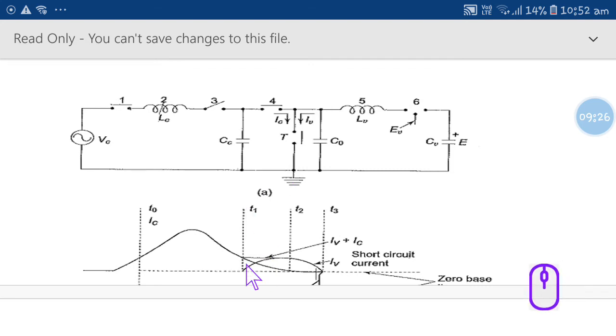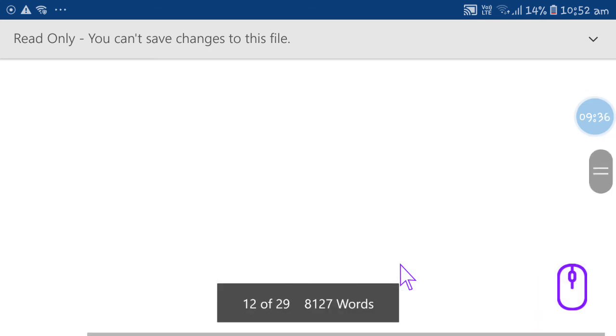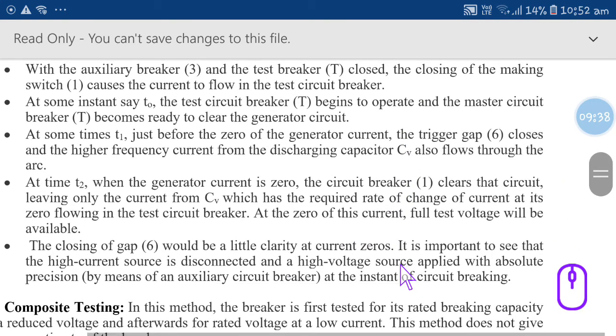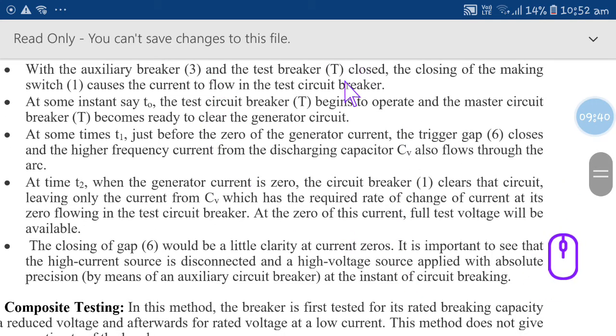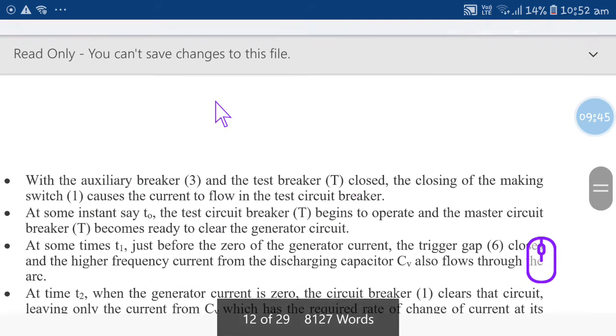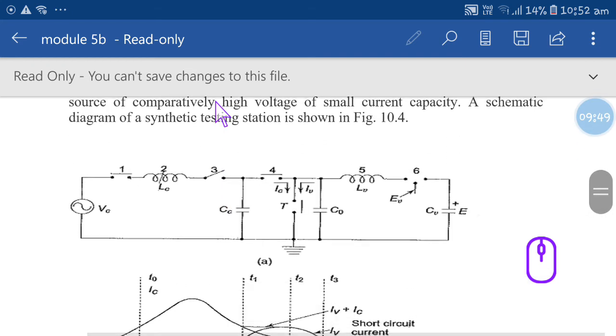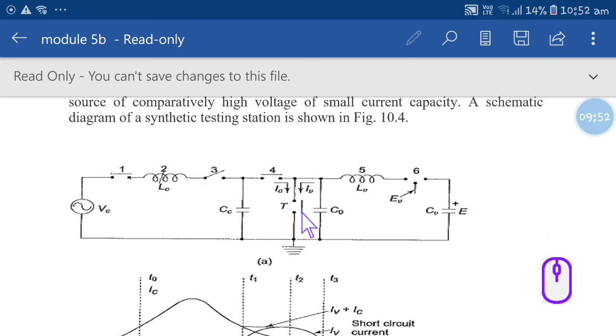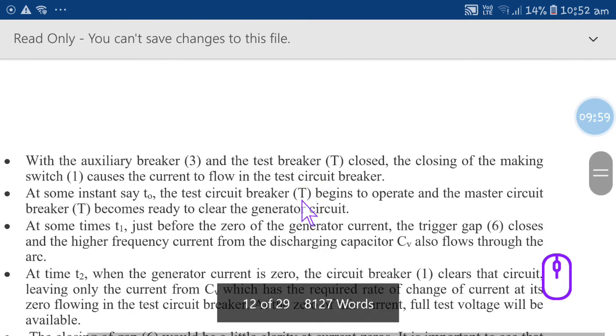And these are the different time periods where the current will rise and come down to the original position. This is the short circuit current you can call, and this is the 0 where the current is interrupted. Just you can see this explanation also. So auxiliary switch 3 and test circuit breaker T are closed. Now this switch 1 causes the current to flow, and 3 and the test circuit breaker T, mainly they have told here. So first they will close these two, it will operate and current will pass. The circuit breaker has to operate here. That only they have explained here.